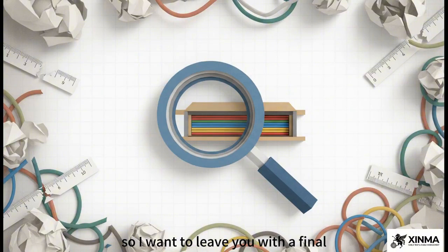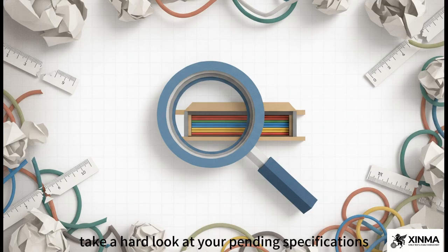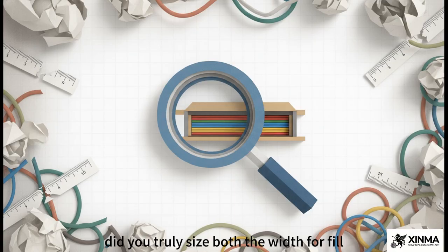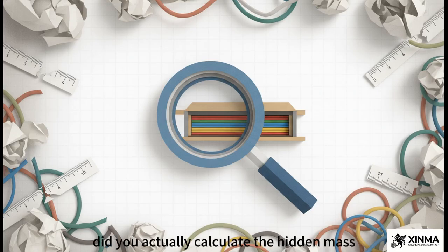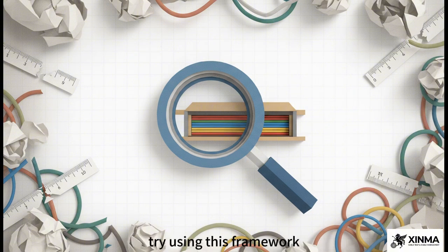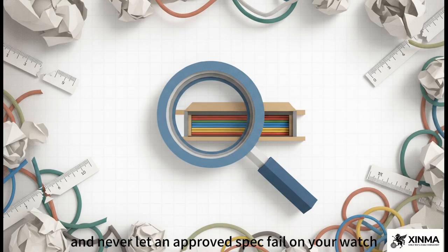So I want to leave you with a final, somewhat provocative thought for the day. Go back to your desk today. Take a hard look at your pending specifications, the ones waiting for review or even the ones that just got stamped. Did you truly size both the width for fill and the depth for stiffness and ventilation? Did you actually calculate the hidden mass of your splice plates and covers? Or did you kind of just guess one variable to satisfy the other? Try using this framework, isolate those dimensions, and never let an approved spec fail on your watch again.